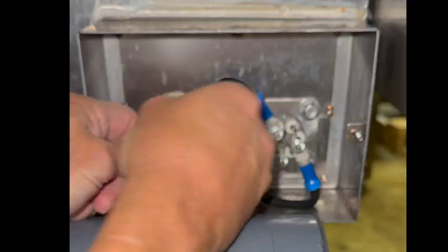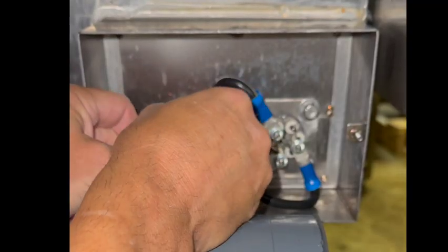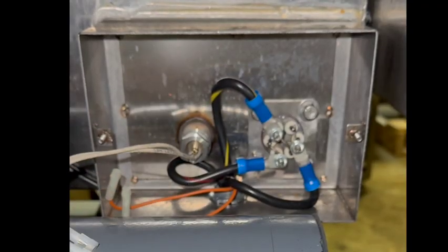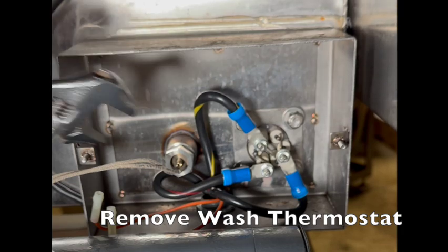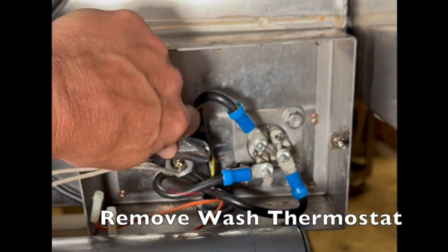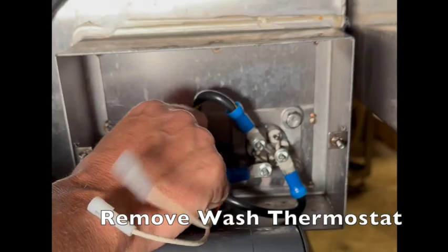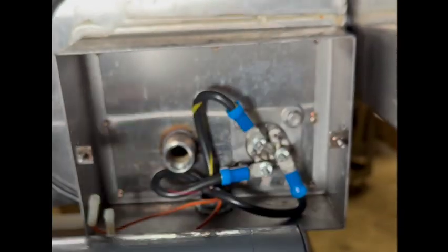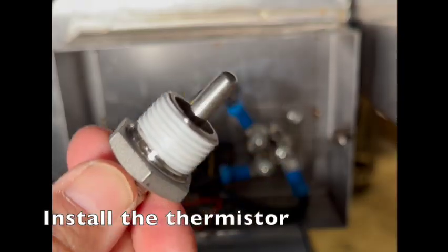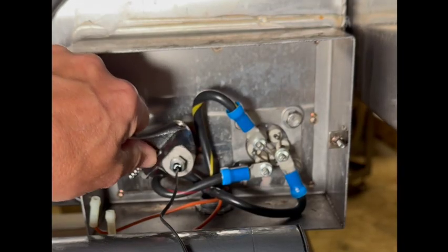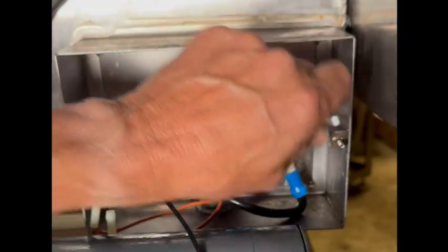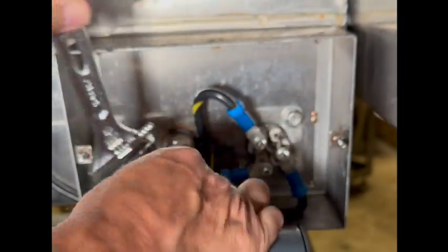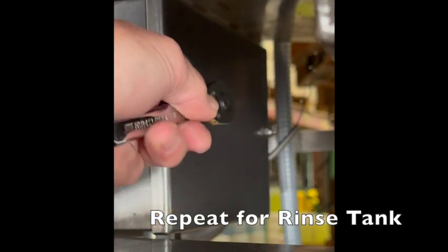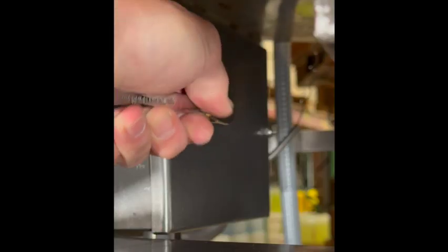Disconnect the 2 orange wires coming from the heater control box to the thermostat. Now you can just get an adjustable wrench in here and remove that thermostat. After you have removed the thermostat, go ahead and replace it with the thermistor that comes in the kit. Just make sure you put Teflon tape or some type of thread material on the threading. Now that you have done the wash thermistor, go ahead and repeat the same process for the rinse tank.